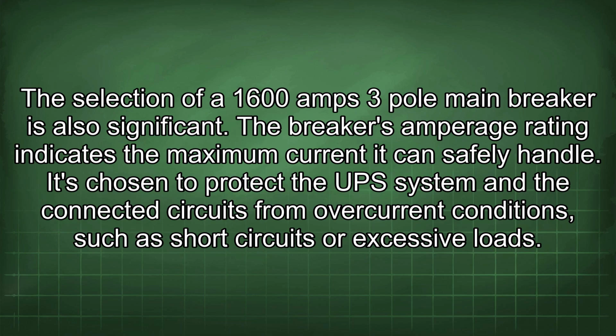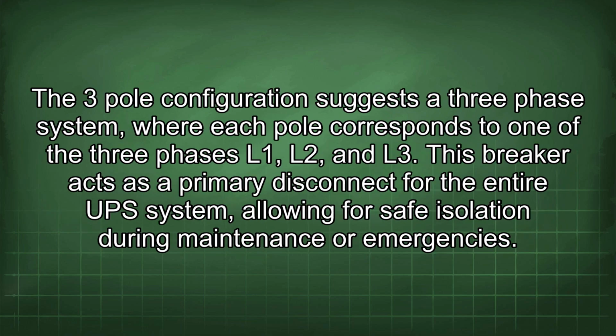The selection of a 1600 amps 3-pole main breaker is also significant. The breaker's amperage rating indicates the maximum current it can safely handle. It's chosen to protect the UPS system and the connected circuits from overcurrent conditions such as short circuits or excessive loads. The 3-pole configuration suggests a 3-phase system where each pole corresponds to one of the 3 phases L1, L2, and L3. This breaker acts as a primary disconnect for the entire UPS system, allowing for safe isolation during maintenance or emergencies.